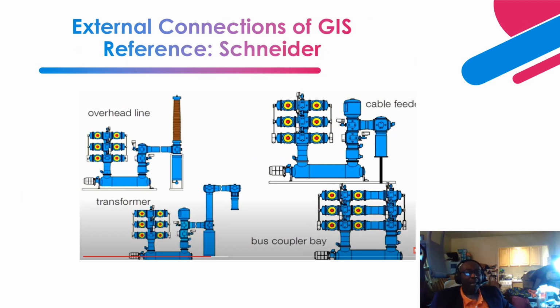Next are the different external connections to your gas insulated switchgear. The first one is an overhead connection. This one is a single phase arrangement. For a 3-phase view, you have phase A, phase B, phase C, on overhead coming in, and then they get connected over here. This is what they call the apparatus bushing. That is the industry technical word for this.